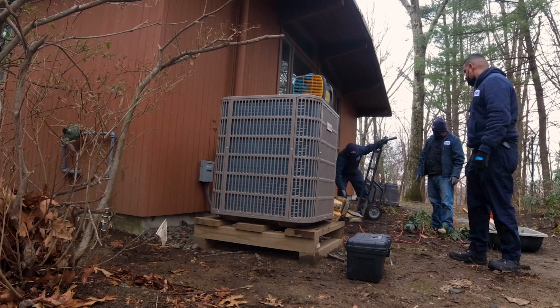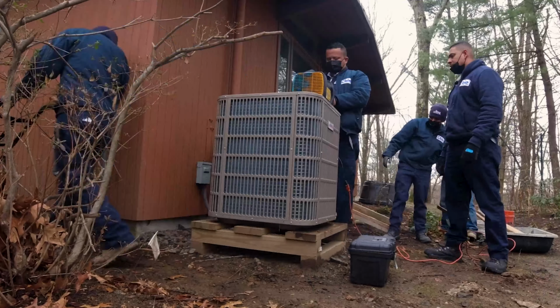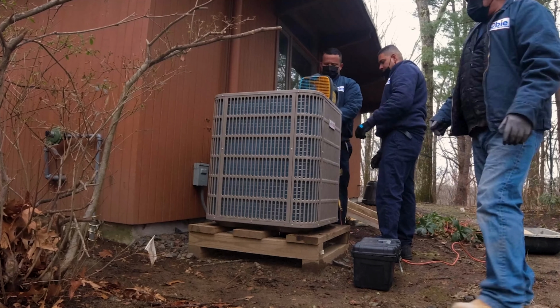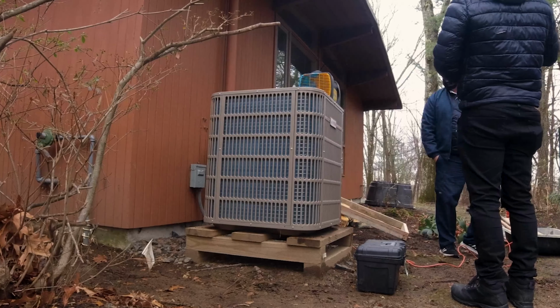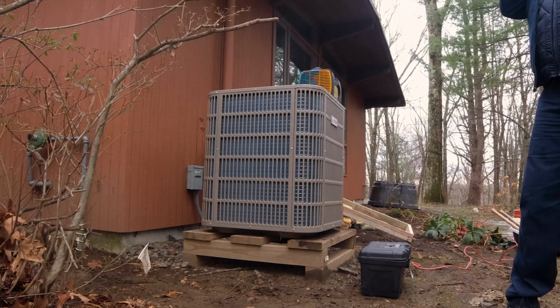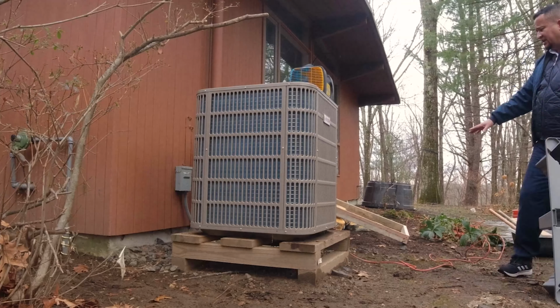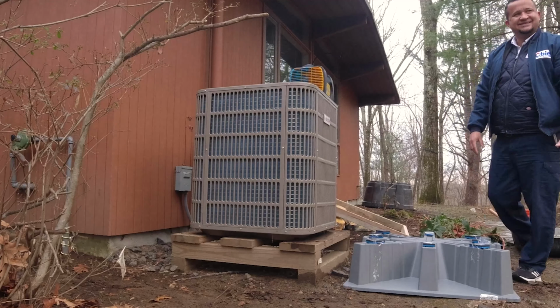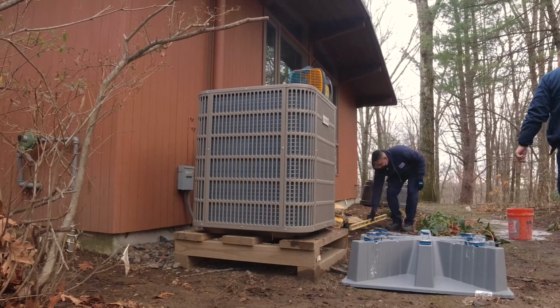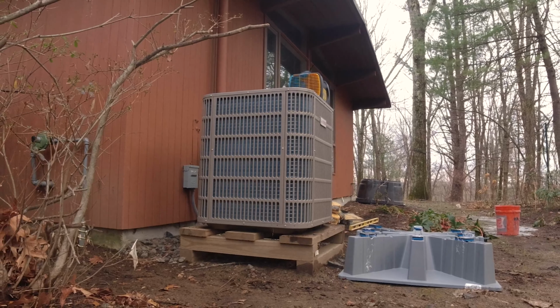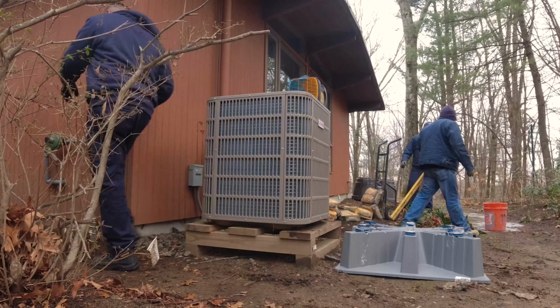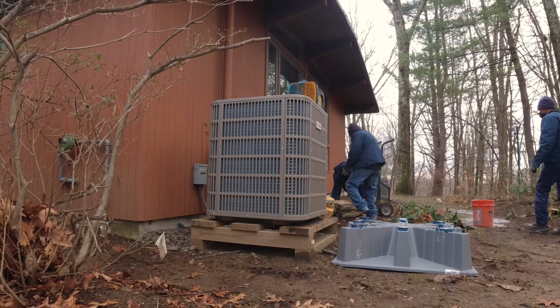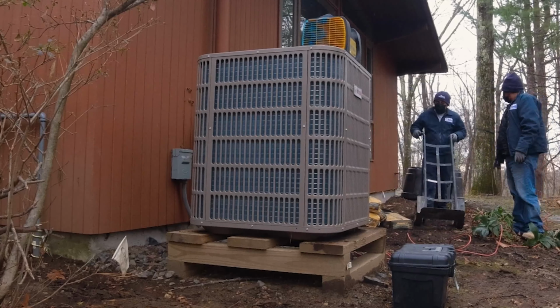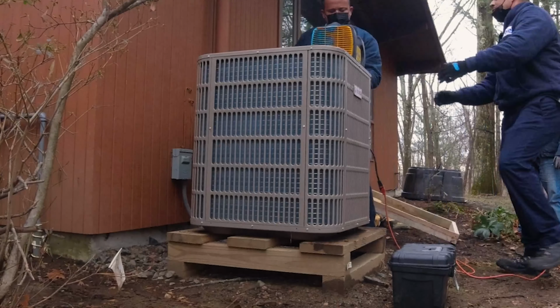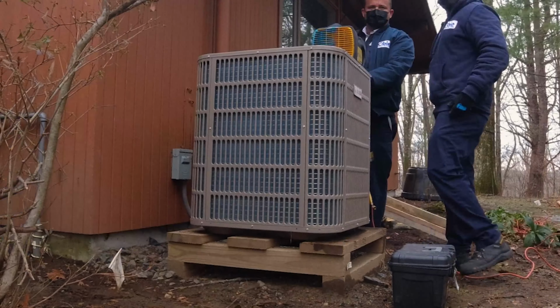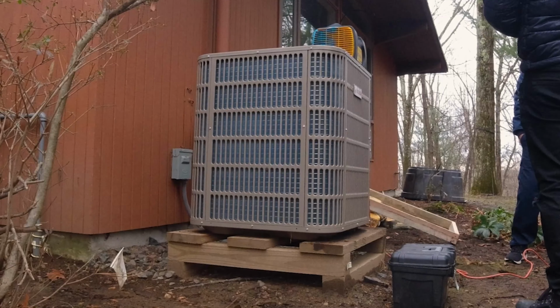Other problems that we see outside is the way they did the pad. A condenser has to be lifted from the ground because with the frosting, some ice can form. Imagine here in the day with the snow and very cold, so they have to lift it. But instead of using the proper pad, they just made one out of wood, and unfortunately it's not even made out of pressure treated wood that would be more resistant. It's just regular wood. They slapped this together. Feels like they just cut a pallet and put the heat pump on top of the pallet.